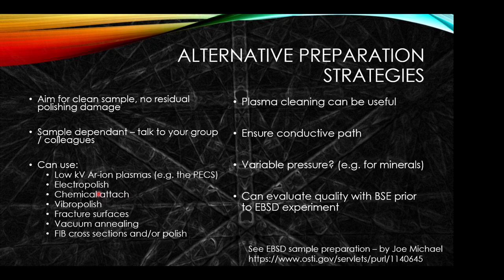In some materials a vacuum annealing process can clean up and remove surface defects. You could do FIB cross-sectioning and FIB polishing for certain samples like particles — for instance if you want to look inside gas atomized particles. Plasma cleaning of your samples will be useful to remove hydrocarbons, which can be particularly bad in terms of contamination especially at the high probe currents, voltages, and long dwell times for EBSD. You want to ensure a conductive path in your sample. For some mineralogy experiments you may want variable pressure, and you can evaluate quality with backscatter electron imaging prior to the EBSD experiment.